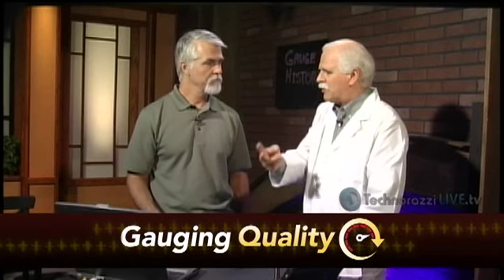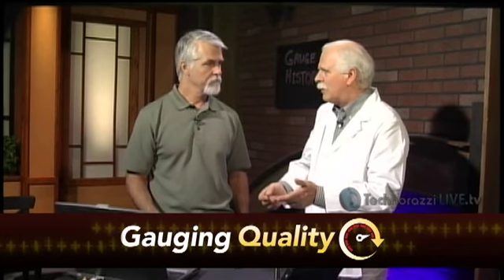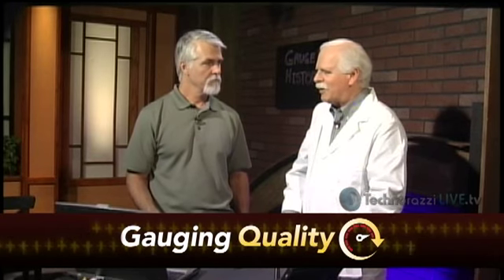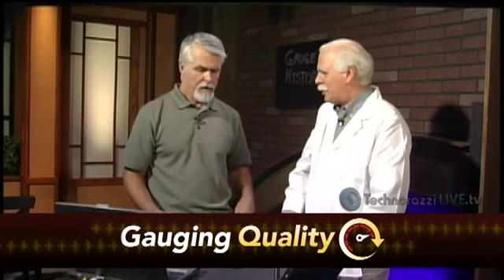Then we'll use an optical parallel, which uses that same principle of light bands. They're extremely parallel, and we'll close it down until it contacts both anvil and spindle. Now, instead of counting the curvature of the light bands to see the flatness, we'll count the total amount shown on the anvil. Say it's 2, and the spindle has 3. You subtract them, you get a difference of 1, and one light band rounds off to 12 millionths. It's 11.999, which rounds off to 12 millionths, so you would know the parallelism.